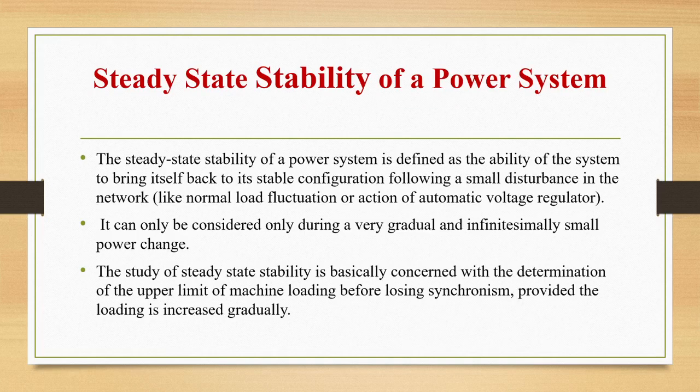Steady state stability is the ability of the system to bring itself back to a stable configuration following a small disturbance in the network. It can be considered only during a very gradual and infinitely small power change. The study of steady state stability is concerned with the determination of the upper limit of machine loading before losing synchronism, provided the loading is increased gradually.